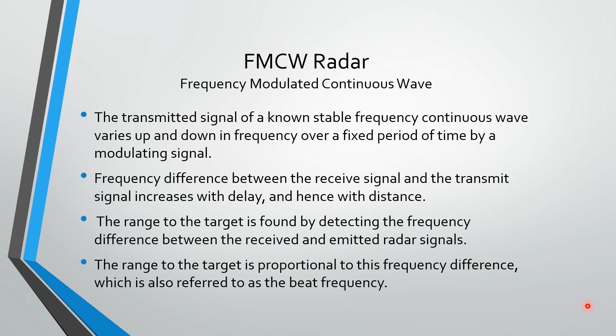The frequency difference between the received signal and transmit signal increases with delay and hence with distance. So we're not only looking at the time, we're also looking at the shift in frequency, looking at both to determine where our level is at. The range to the target is proportional to the frequency difference, sometimes referred to as the beat frequency. So that's frequency modulated continuous wave, a linear frequency modulated continuous wave.